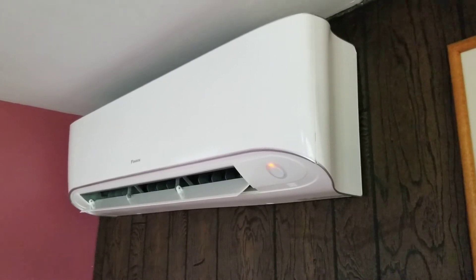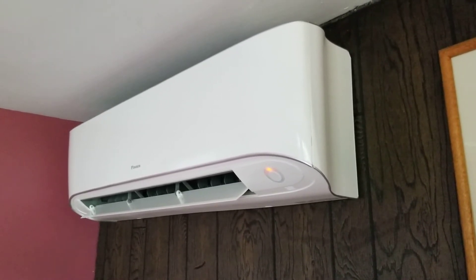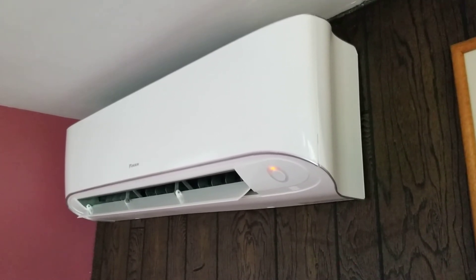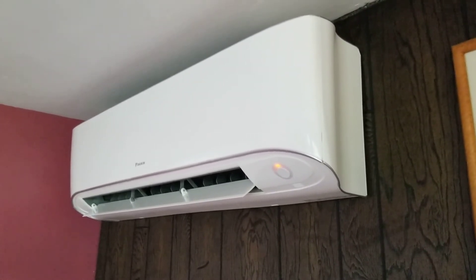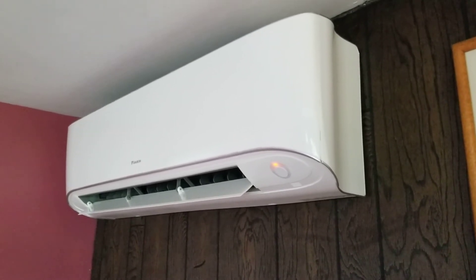Your efficiency is barely less. We're talking 17 SEER and 9 HSPF compared to, what, like 20 SEER and 10.6 HSPF. That's not a huge thing. And I'm not so sure that the outdoor units aren't the same thing anyway — it's just a different indoor head.